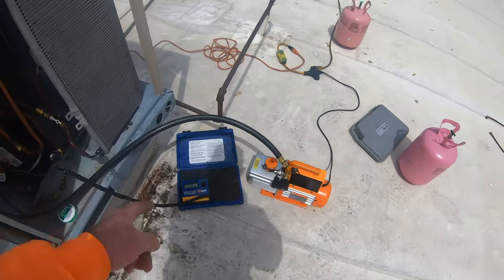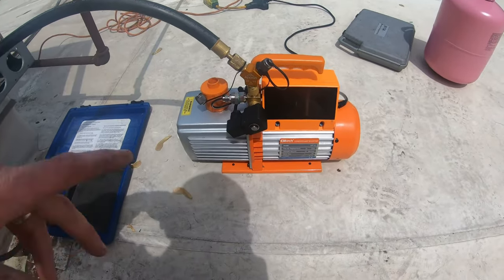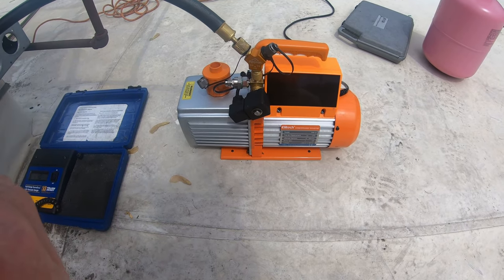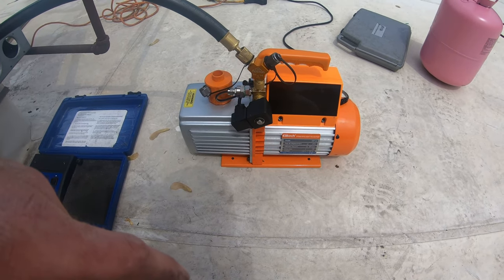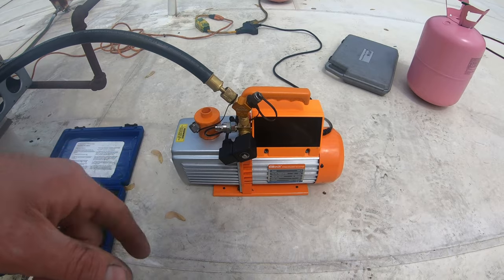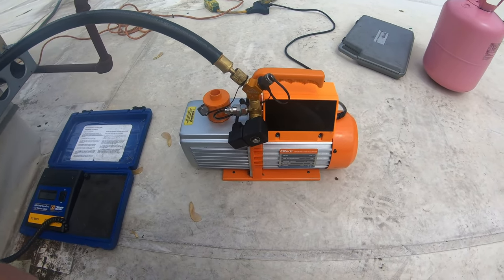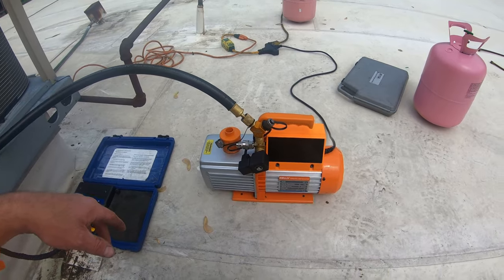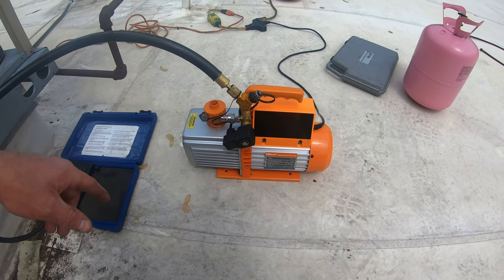We had a quick lunch and things are looking really good. We're going to start doing a cleanup and charging this thing shortly — we should reach our vacuum momentarily. Just wanted to give you guys a little video on the Elitech SVP12, 12 CFM vacuum pump. If you're interested, I've got links in the description to check it out from Elitech and Amazon. It's showing microns at 269 on this one, and we're about at 500 on the Yellow Jacket. I appreciate you guys watching — check out those links in the description for the Elitech SVP12, and I'll see you on the next one.